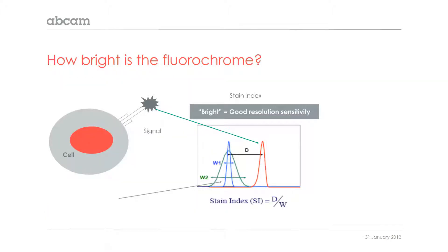The stain index is depicted by the signal from the cell, which is depicted by the positive peak, but it's also depicted by the width of the autofluorescence. The stain index is the distance from the negative to the positive divided by the width or standard deviation of the negative population. The standard deviation is very important because, if we take a narrow peak, the distance from the positive to this narrow peak is far greater than if you have a highly autofluorescent cell, such as mesenchymal stem cells or embryonic stem cells, as opposed to lymphocytes. So the stain index will vary from cell type to cell type, as well as from instrument to instrument.